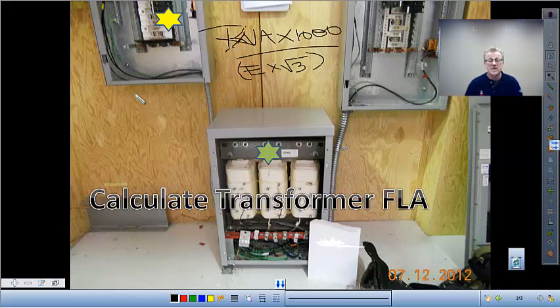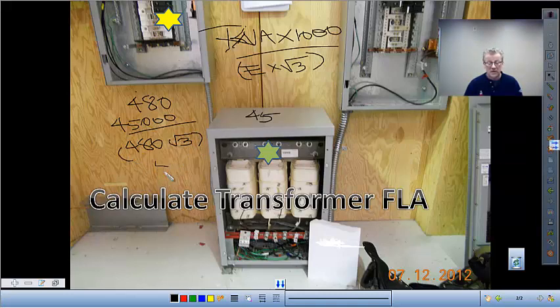For the case of, let's say this was a 45 kVA transformer and a 480 volt primary, that would result in a current, 45,000 divided by 480 and the square root of 3, and you'll get something like 54 amps, somewhere in the neighborhood.